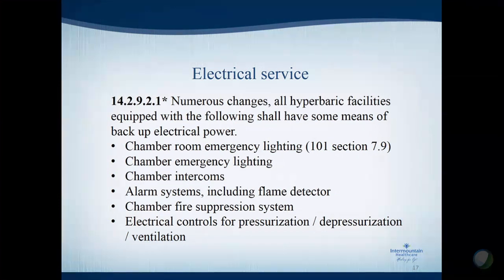Now, I won't go into all the changes we made in electrical service. In 14.2.9.2.1 with the annex notes, we made numerous changes. The main thing we were looking at was that not all hyperbaric facilities have a backup generator. There are all kinds of horror stories coming out of the CMS adopting NFPA 2012. They're requiring, even for facilities that only do wound care Monday to Friday and don't have a generator in the building for any of the services in that building, a surveyor requiring that they install a generator. So we added some language to try to help that.